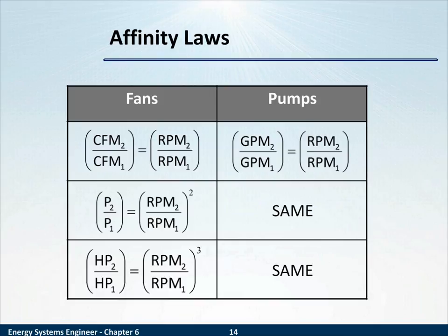And all of these losses are opportunities for savings. The reason we bring up the affinity laws is to put in context the previous slide that showed several losses. This slide shows that not all losses are considered equal. For fans or for pumps, the affinity laws are very similar. If you want to consider pumps, just use gallons per minute instead of cubic feet per minute. But let's consider the fans, just to use that one because of the similarities.